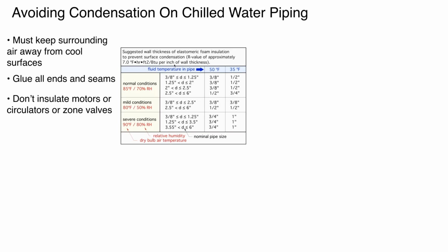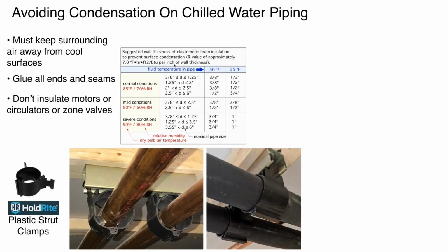I'll cut to the quick. 1/2-inch elastomeric foam will stop condensation in just about any typical application. I mean, if you're in a sauna with extreme humidity and you're working with 35-degree fluid, you might want to go to a thicker insulation, maybe 3/4 inch, but 1/2-inch elastomeric foam works pretty good.